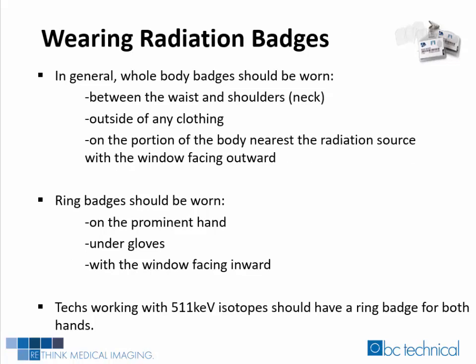Let's talk about wearing radiation badges. In general, whole body badges should be worn between the waist and shoulders, outside of any clothing, and on the portion of the body nearest to the radiation source with the window facing outward. Ring badges should be worn on the prominent hand, under gloves, and with the window facing inward, toward the source. Technologists working with 511 keV isotopes should have a ring badge for both hands, and they should be changed monthly.